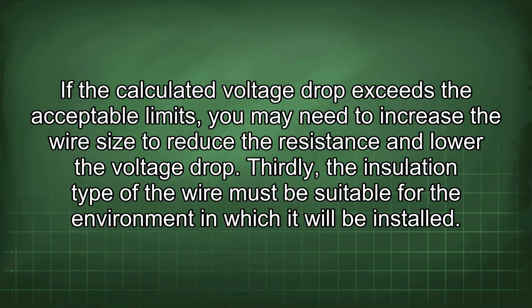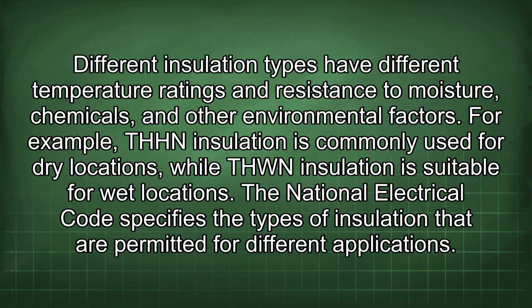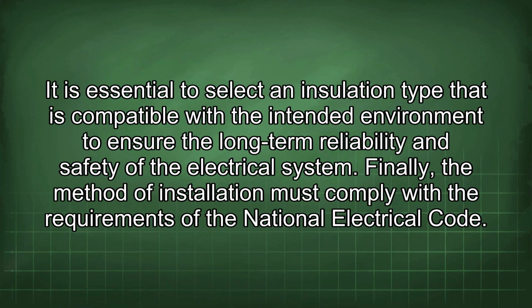Thirdly, the insulation type of the wire must be suitable for the environment in which it will be installed. Different insulation types have different temperature ratings and resistance to moisture, chemicals, and other environmental factors. For example, THHN insulation is commonly used for dry locations, while THWN insulation is suitable for wet locations. The National Electrical Code specifies the types of insulation that are permitted for different applications. It is essential to select an insulation type that is compatible with the intended environment to ensure the long-term reliability and safety of the electrical system.